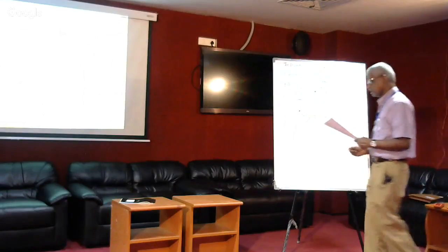And I have to convert the liters per day into liters per minute because I have an EBCT. So this translates to 173.6 liters per minute. A day is 24 hours and an hour is 60 minutes, so if I divide this by 24 and then further divide by 60, this is what I get. Okay.